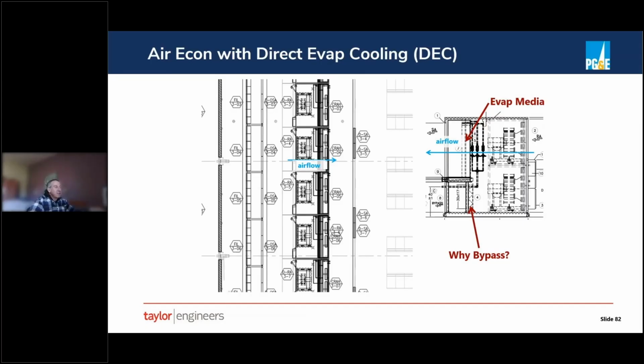The freeze protection would come primarily from your economizer dampers, right? Your outside air and your return damper. Even if it's 0 degrees outside, you're going to be blending outside air and return air. So you're mostly going to be returning air and blending it with outside air. And so if you were going to do, say, evaporating water to raise your humidity in the winter, you're sort of protected by your economizer mixing. If you don't care about low humidity, then you would never run your evap when it's cold out. You would just be on a pure economizer. But thank you for hazarding a guess. Anyone else want to hazard a guess?